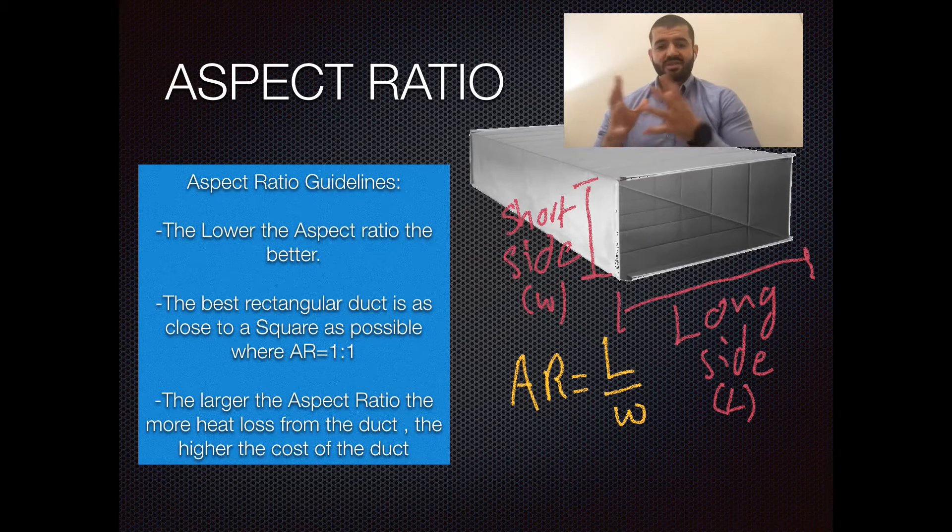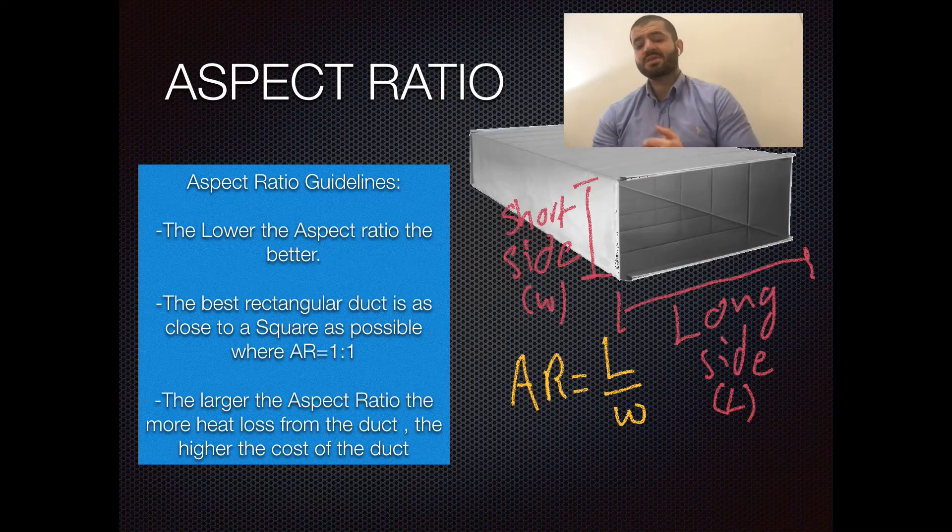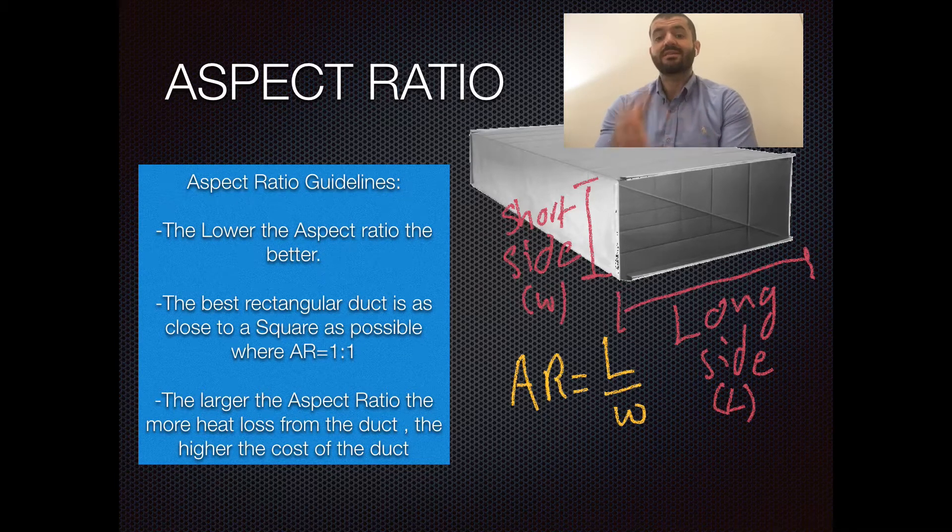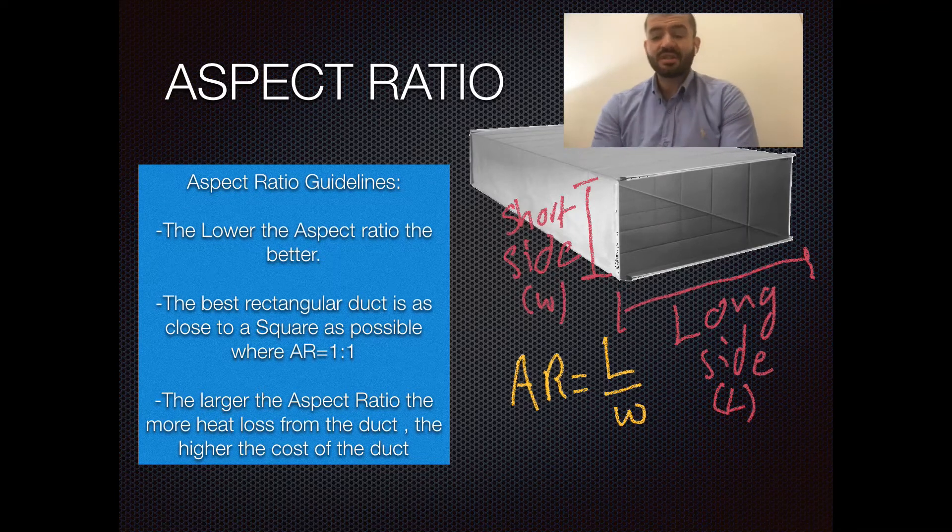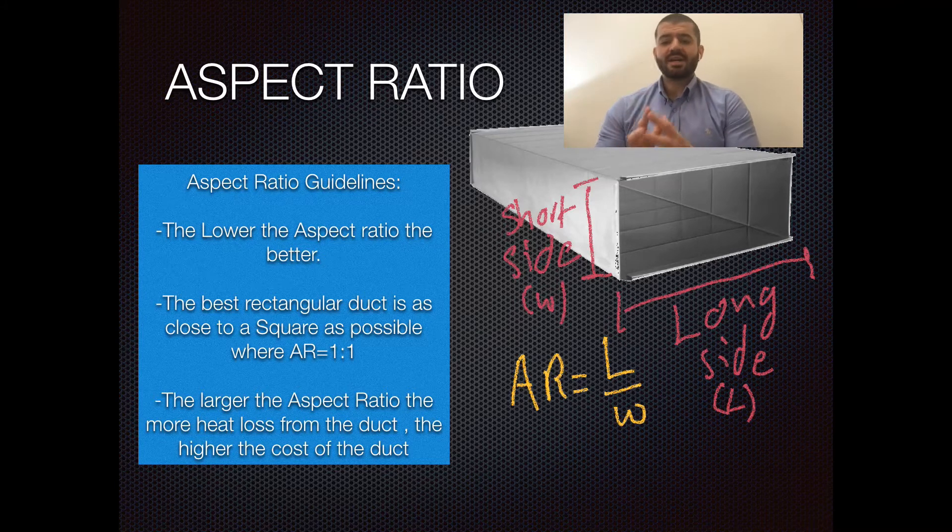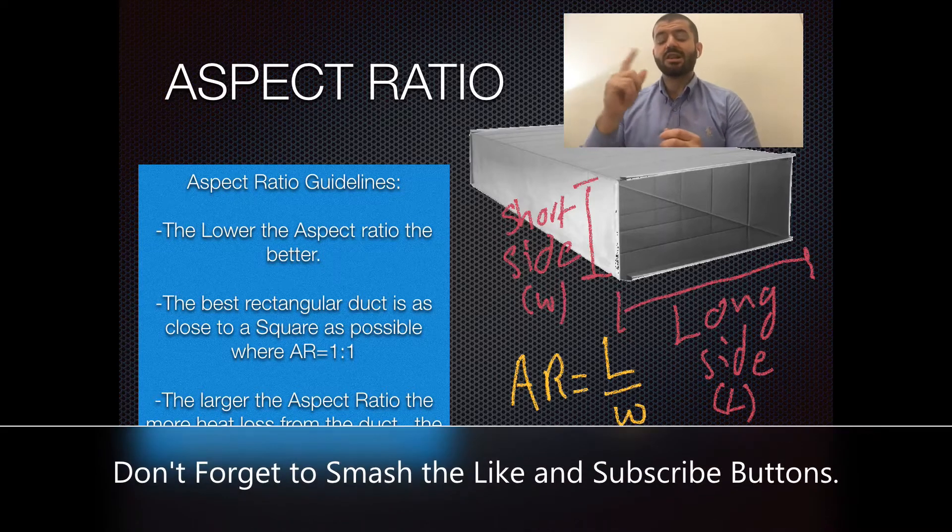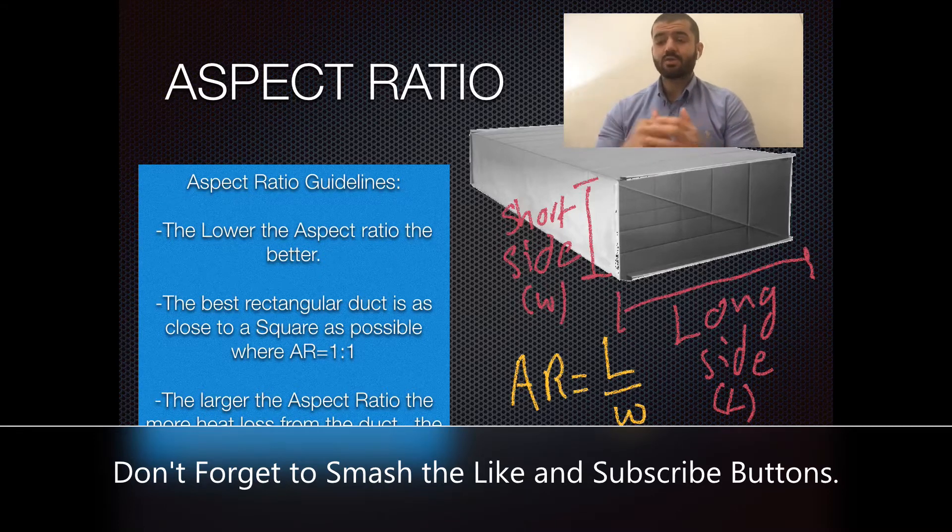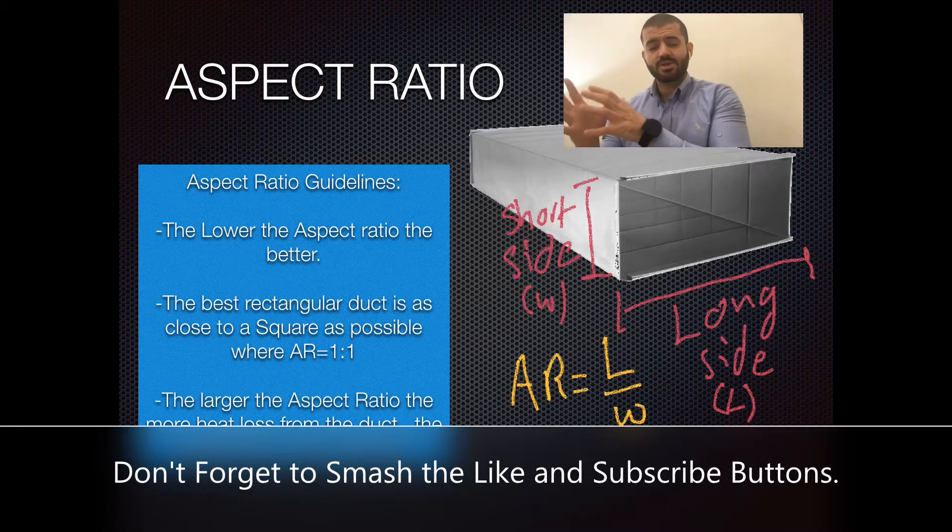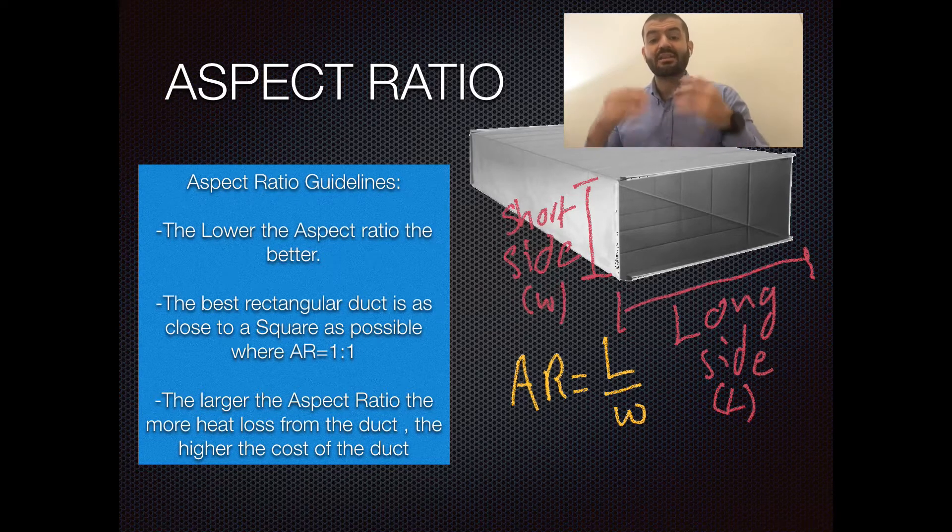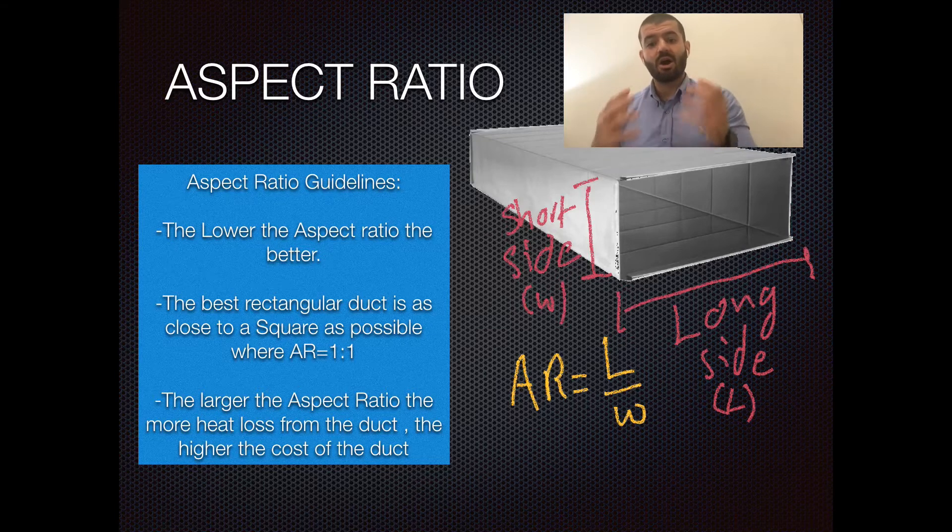Now, the aspect ratio is the ratio of the long side of the duct to the short side of the duct. Let me tell you why it's a very important parameter that should be taken into account during the duct design process in general, and especially in the duct sizing process. As you can see from the formula, you have the long side at the top and the short side at the bottom. From a mathematical point of view, the larger the long side and the smaller the short side, you'll have a higher aspect ratio. High aspect ratios mean your air flowing through the ducting system will be in contact heavily with the walls of the duct.